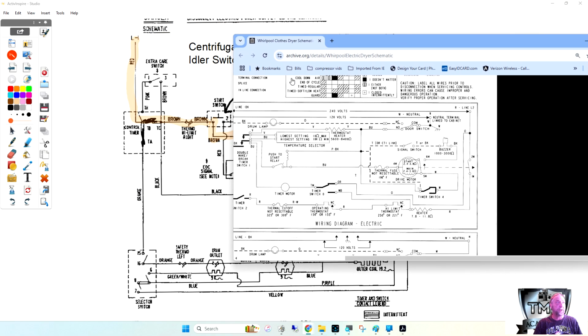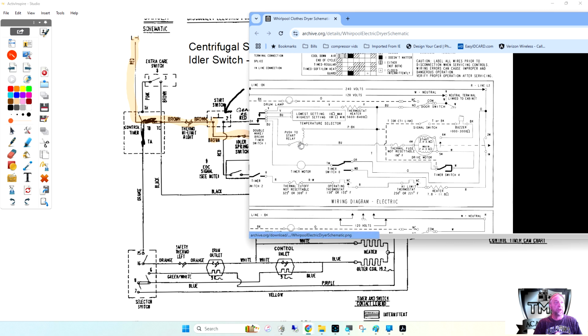Let me just move it over here. If you look, here's a push to start relay. It has 3 terminals on it with a magnetic coil. This only has 2 terminals on it. Okay? And when you let go, there's another wire here that bypasses it. We don't have any other way to send power to the motor except through that switch. So if this one failed to keep the motor running after you let go, it could be a defective switch. The coil could be bad, not the actual contact, because if the motor ran at all, the contact's good, it's just the coil's not maintaining it closed.